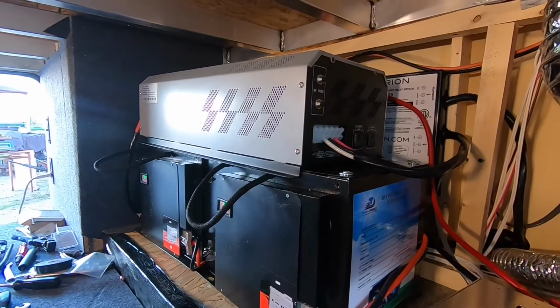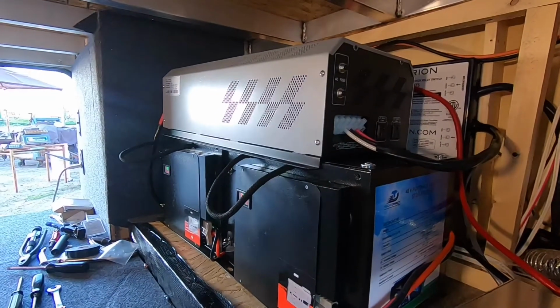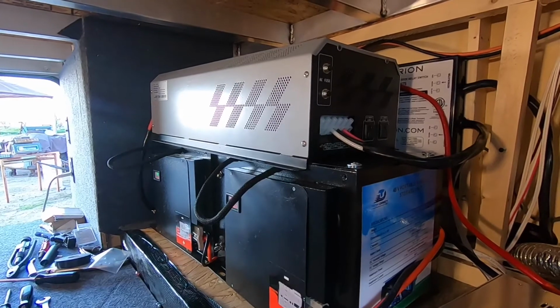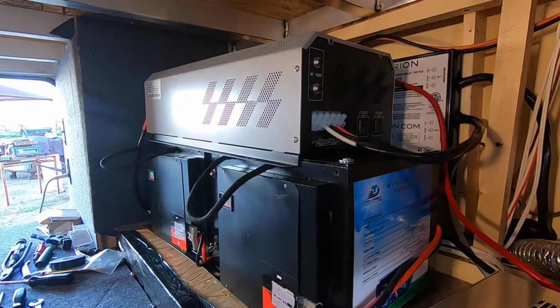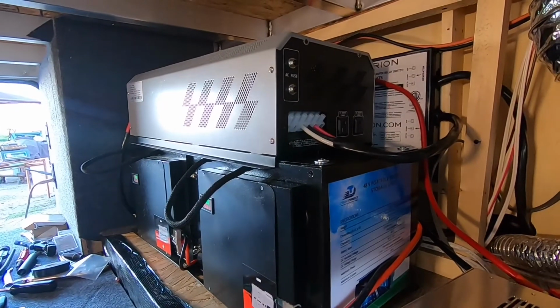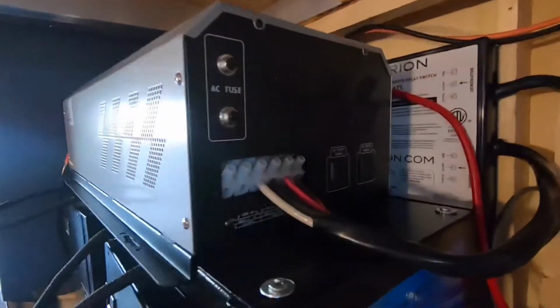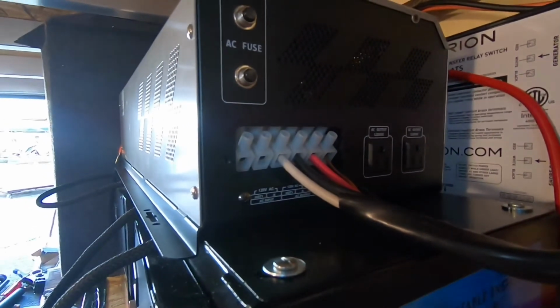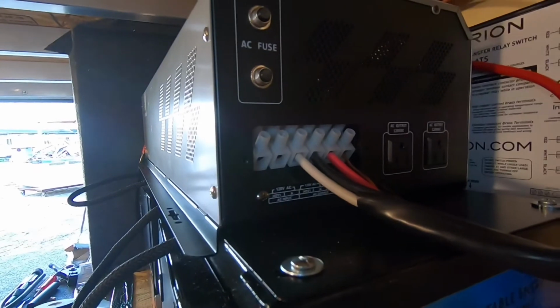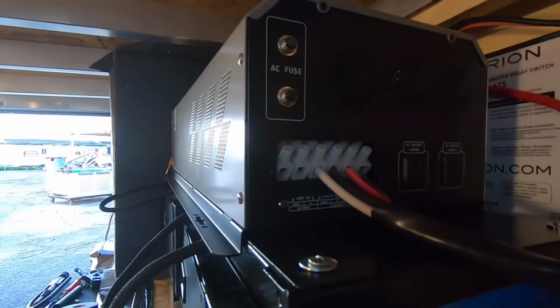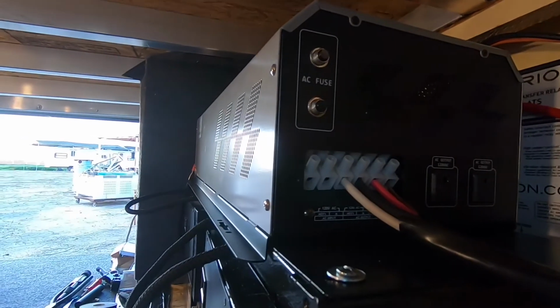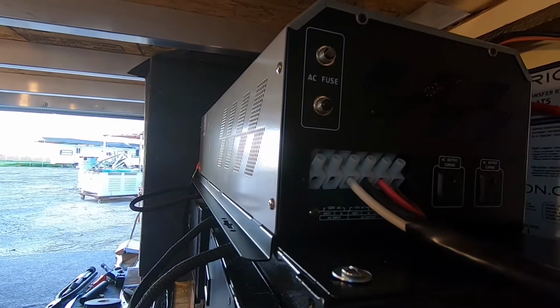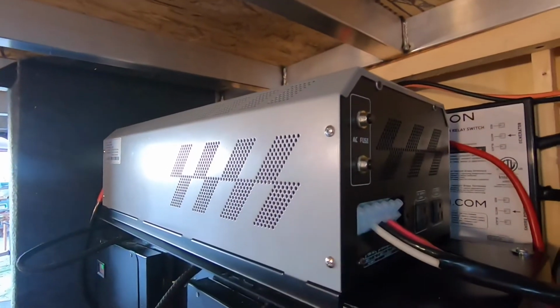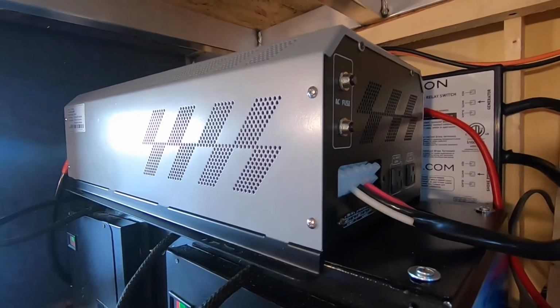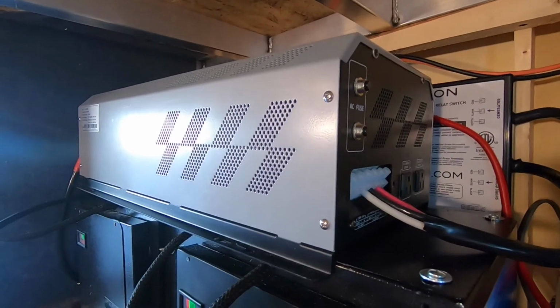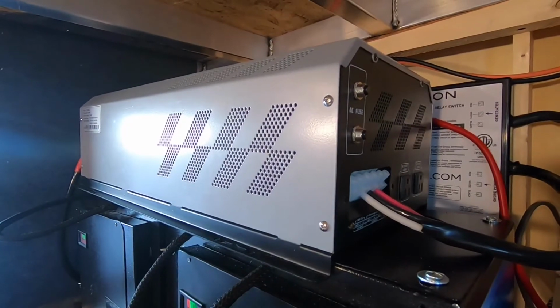So fortunately I was fast enough to shut this down before it short-circuited badly enough to burn up. But if you buy this inverter, or any inverter, check the leads to make sure your hots are where they're supposed to be hot and your neutrals are where they're supposed to be neutral, because mine was not correct. That could have been a very bad situation, destroying not just my inverter but electrical equipment in my RV. It could have been a very expensive day had I not been standing there to shut that breaker off. It was very lucky.